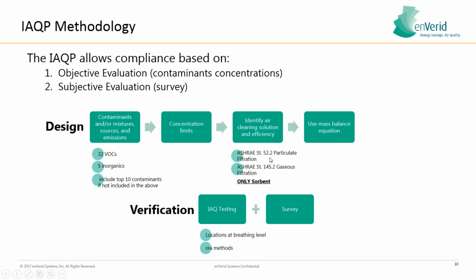ASHRAE 52.2, which we're all familiar with, is what assigns a MERV rating. And then ASHRAE standard 145.2 is gaseous filtration testing. So what is the efficiency of your device in accordance with ASHRAE 145.2 and its ability to remove contaminants like formaldehyde, carbon monoxide, ozone, toluene, benzene, NOx, SOx, BTX from the air without any byproducts. You use the mass balance equation that's within ASHRAE 62.1, and this is a new process for many folks. Trust me, it's not that complicated, and enVerid does it every day for many, many projects, and we're happy to help. And then there is a verification component.